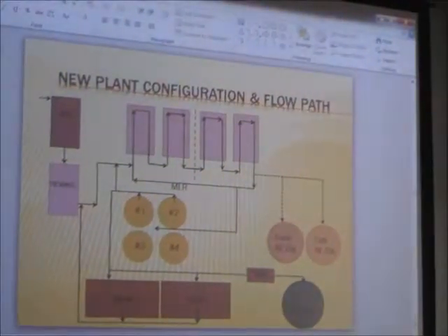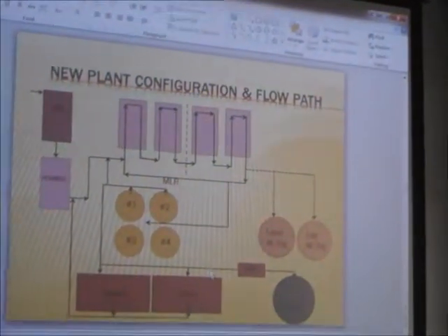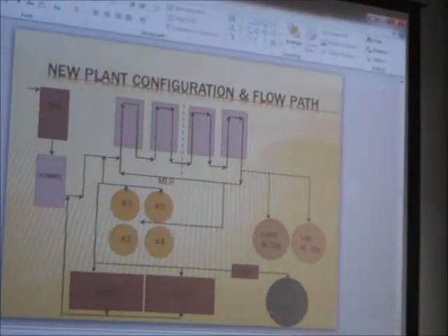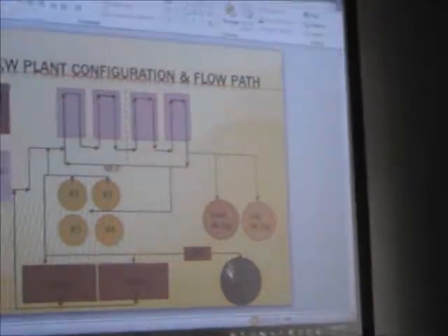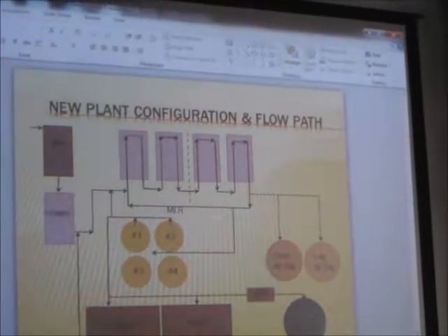And then on the wasting side, we put sludge across the gravity belt thickener. It goes in at, let's say, 1% thickened across the belt to 6%, and currently we pump it into the anaerobic digester. It gets digested and has residence time in there, and then after 40 days or so it's stabilised, and we can draw it off for dewatering and land application.